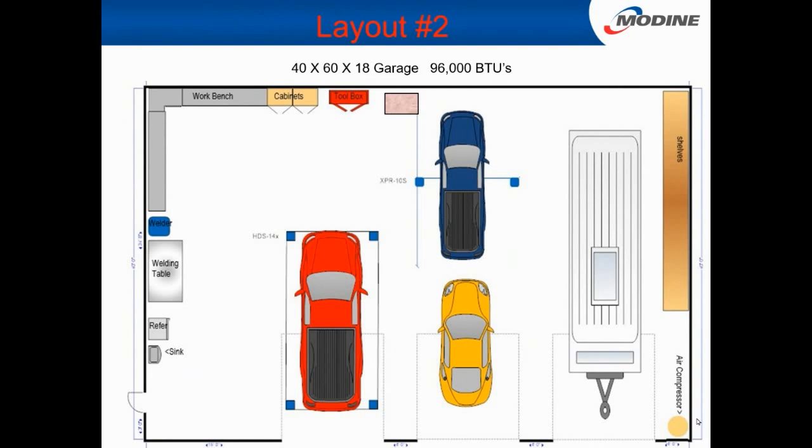Okay, I worked at Thermal for 8 years. Guess where all of their unit heaters are located? Right next to the garage door. They had an engineer, our engineer that worked for us, design this building. And that's wrong. Because every time you go in the garage door, what are you gonna do? You suck all that cold air across that heat exchanger.